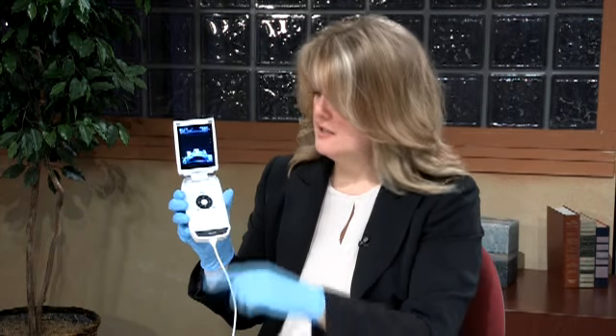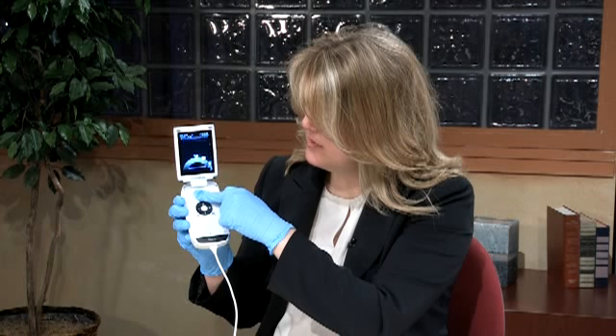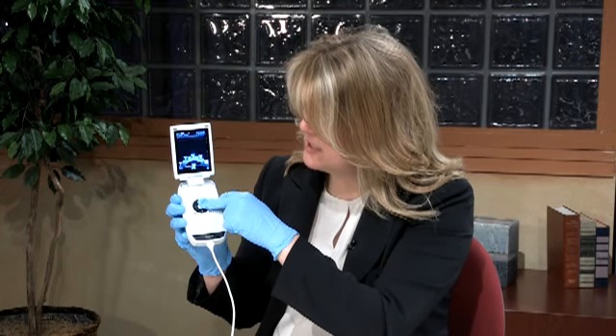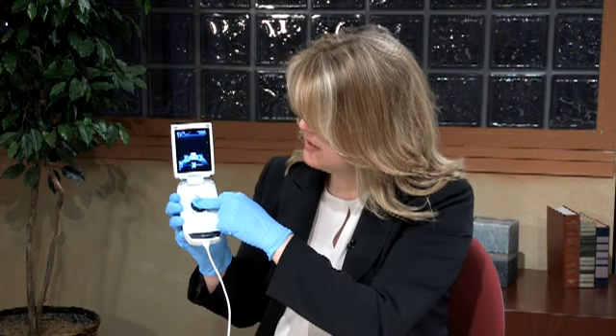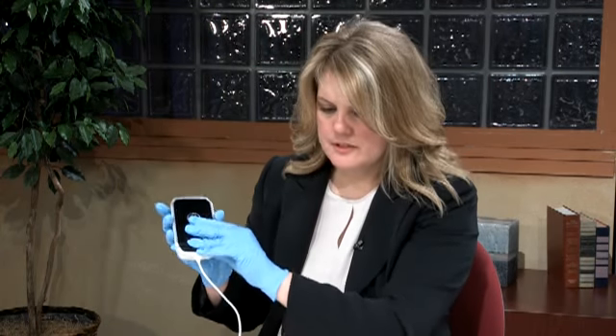Let's review how to clean and disinfect the Vscan with dual probe device. The first step before cleaning the device is to enter Menu and Config to fully shut down the device. By pressing Menu and scrolling over to Config, you see Shutdown is an option closest to me. Selecting Shutdown will help the system completely shut down. Close the device. To clean the device, find a soft, non-abrasive cloth and using a general or mild purpose non-abrasive cleaning material, completely cover and wipe around the device. You can use another soft towel to dry off afterwards.